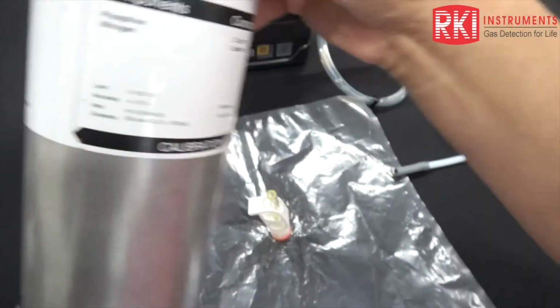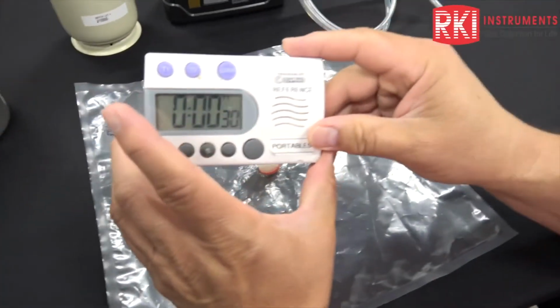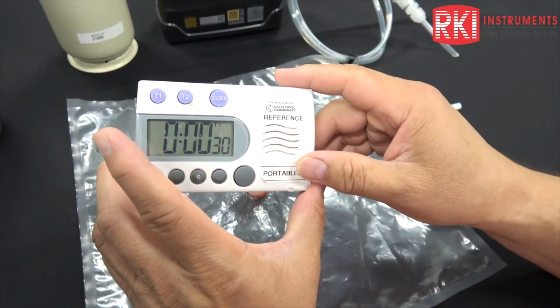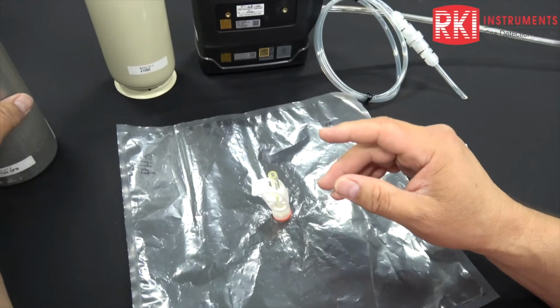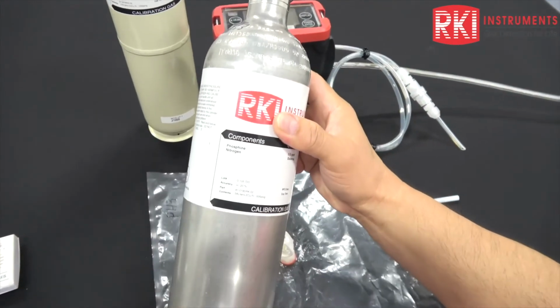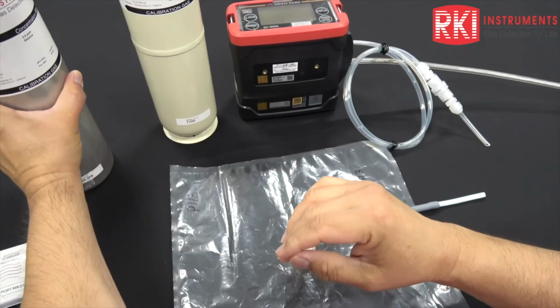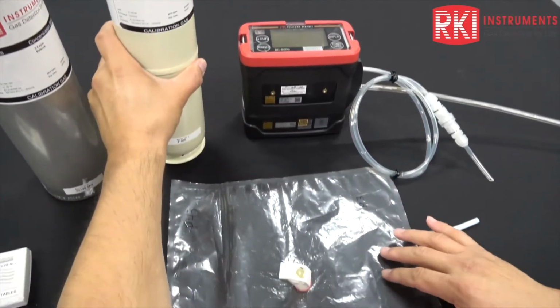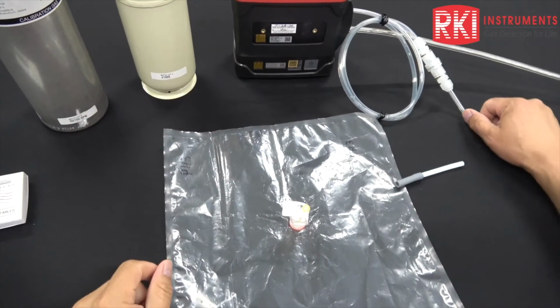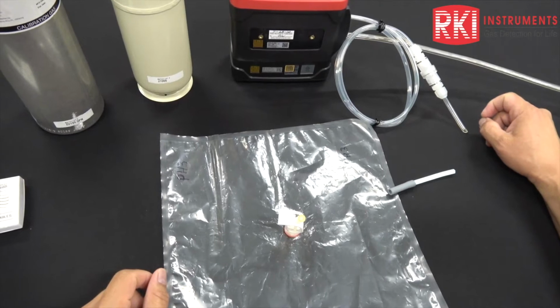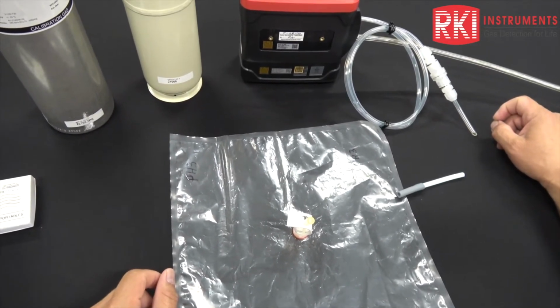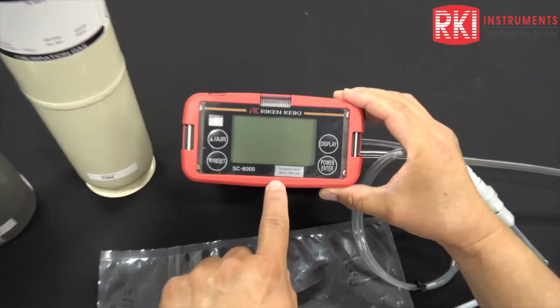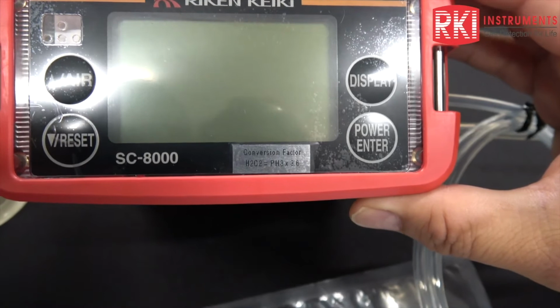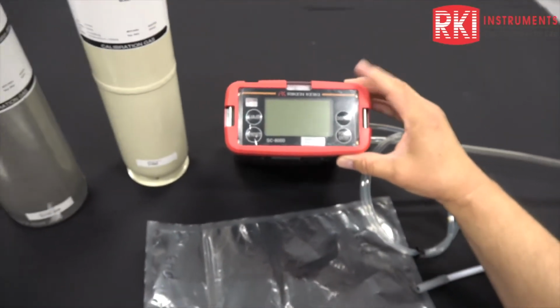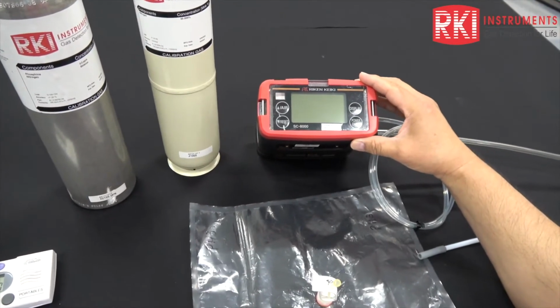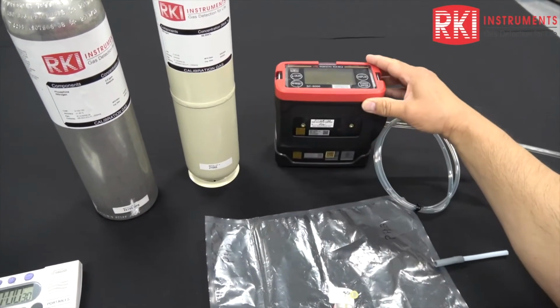So basically, we're going to use a timer here. Any nice timer will do, that gives you control over your seconds and minutes. So basically, we're going to flow 30 seconds of phosphine gas into the bag, and then we're going to flow 2 minutes of the nitrogen into the bag. So that gives us basically a 4-to-1 ratio, or a division of 5. So basically, the 0.5 ppm of phosphine will be diluted down to 100 ppb of phosphine, and then the conversion factor 100 times 3.6 is going to be 360 ppb. So we've got that value set into the unit already, as that takes into account the conversion factor ratio. And we'll go ahead and get started with the calibration.